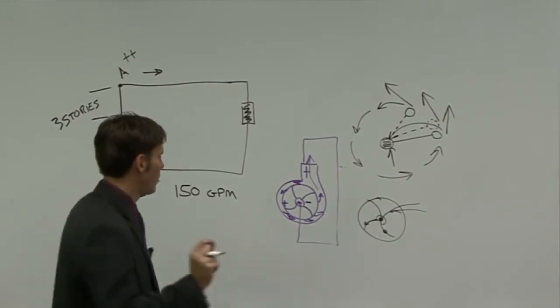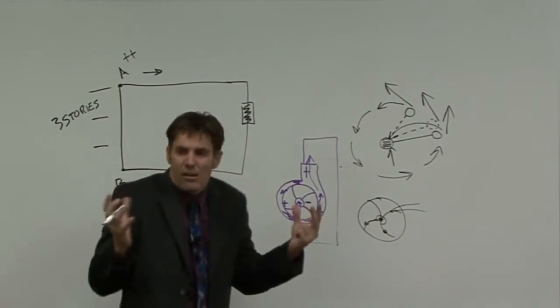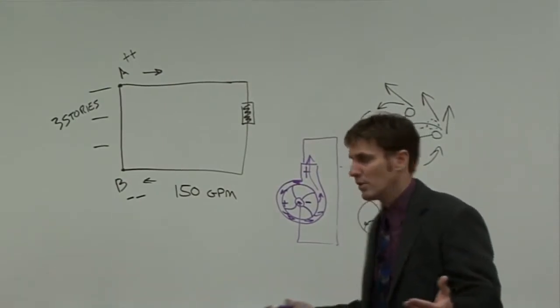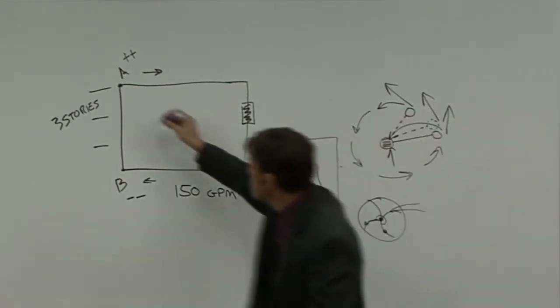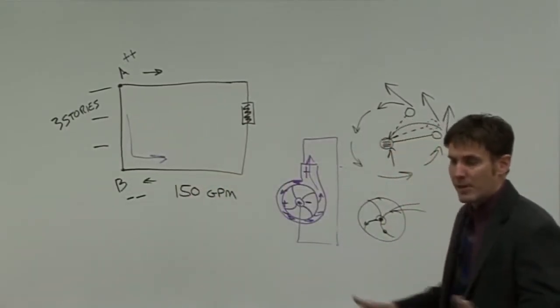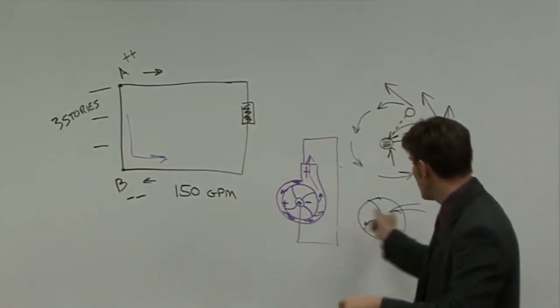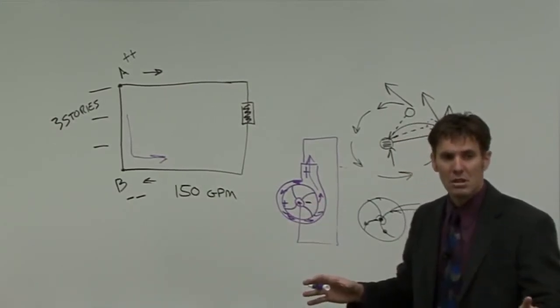That motion creates that differential pressure because of this. Now, I get asked all the time, "Joe, my pump is wired backwards. My pump is rotating backwards. My motor's spinning backwards. Am I going to now move flow in this direction?" If my pump is wired backwards because I'm a three-phase motor, and so we simply cross the lines and now my motor's rotating backwards, my pump is spinning backwards, does that mean I'll now flow in the reverse direction?